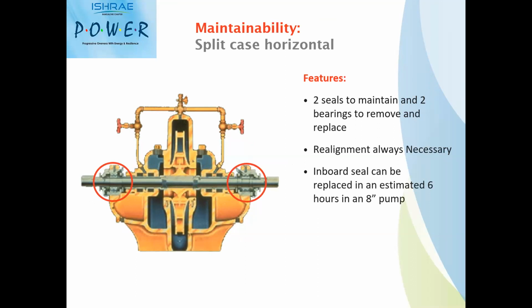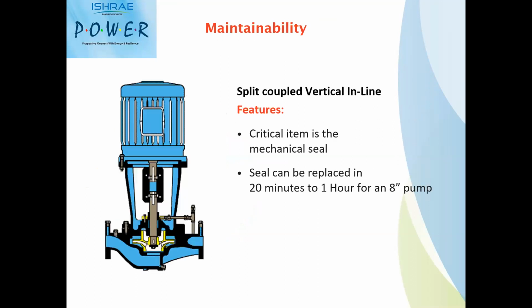So maintainability wise, when it comes to typical vertical inline design, the vertical inline by design itself has very few items, that is parts. Some manufacturers will not have bearings on the pumps, and as well as your base plate is not there. In some manufacturers' case, the flexible coupling itself is not there, it comes with the solid split coupling. So all these lesser number of parts make it easy for maintenance of the pumps when typically compared with end suction or horizontal split case pumping.